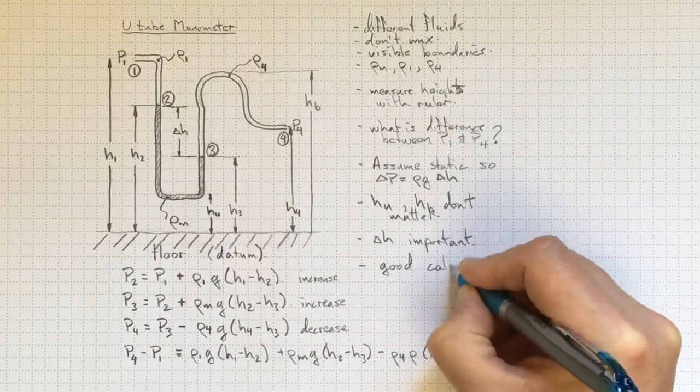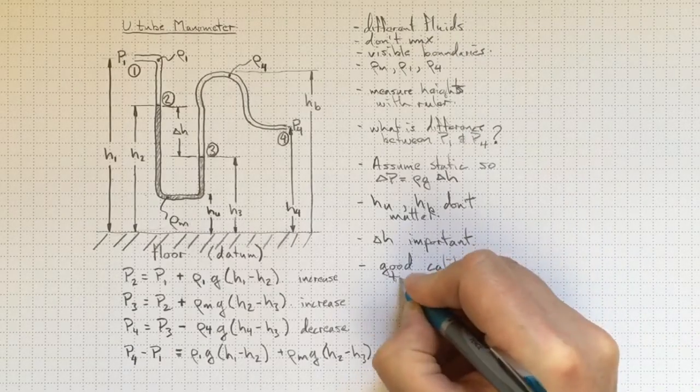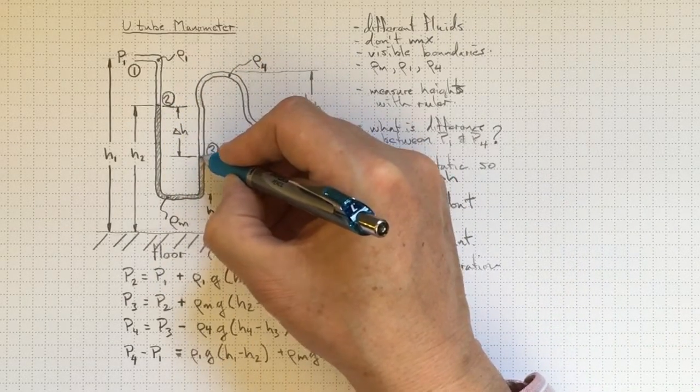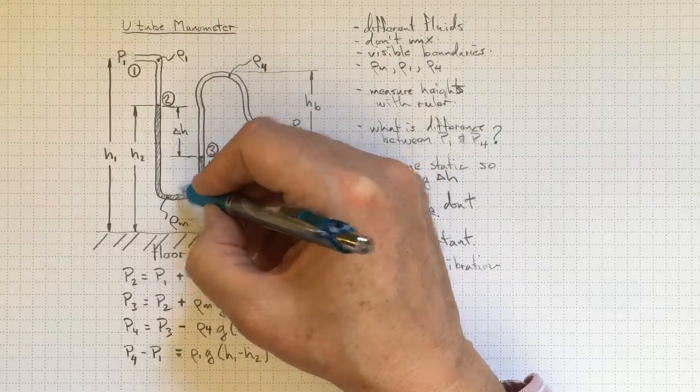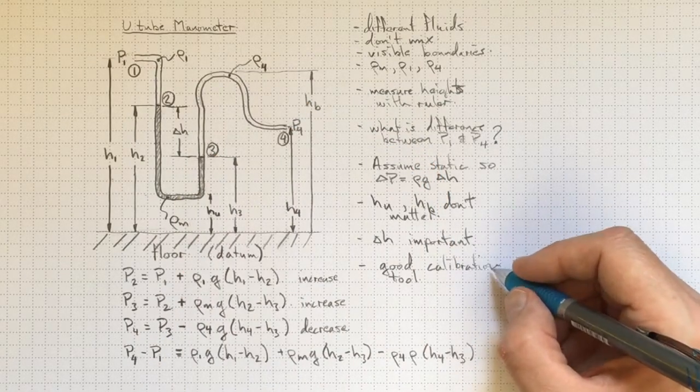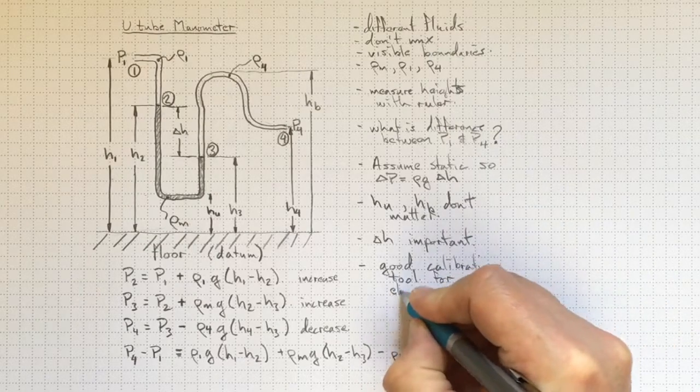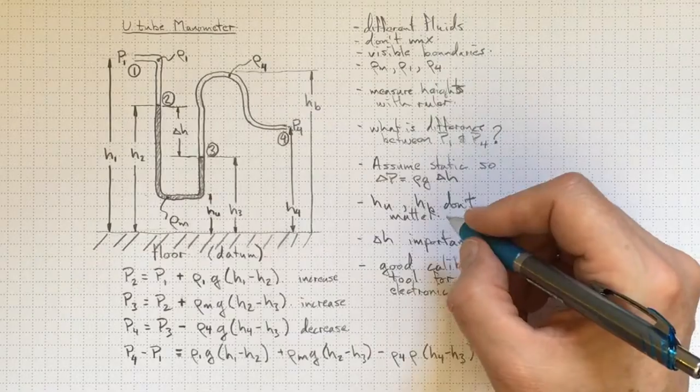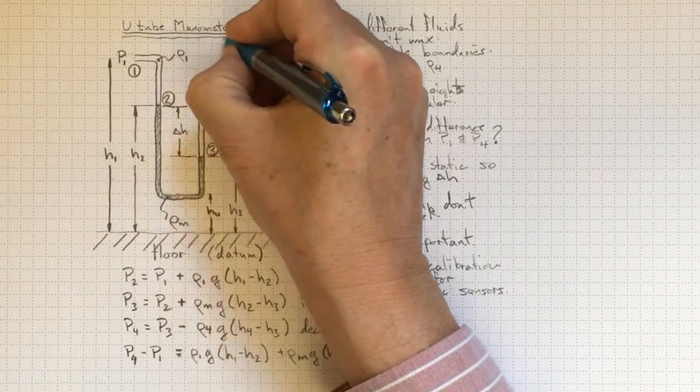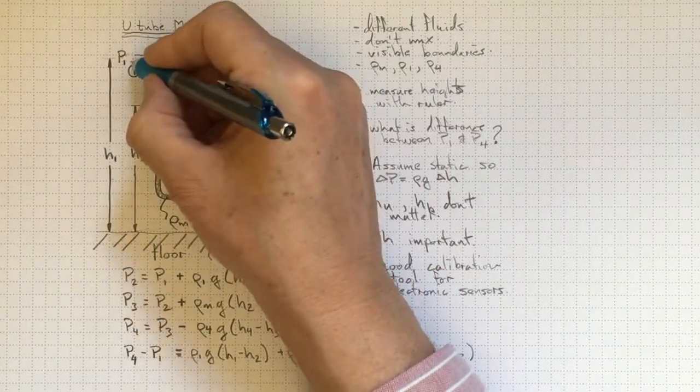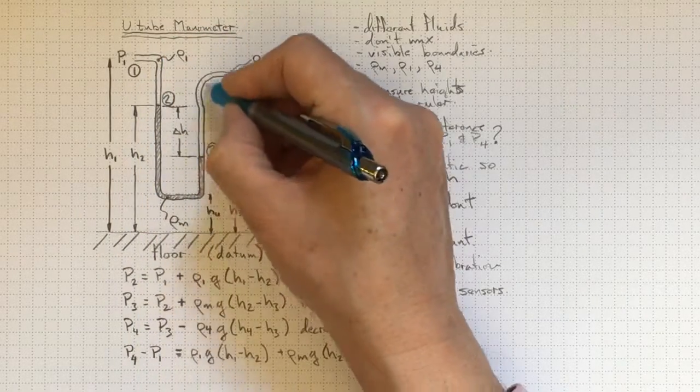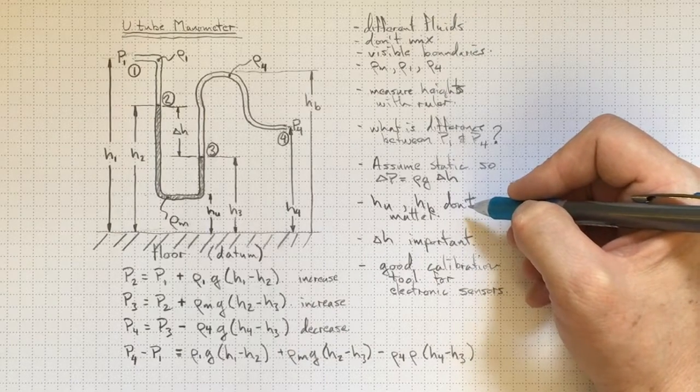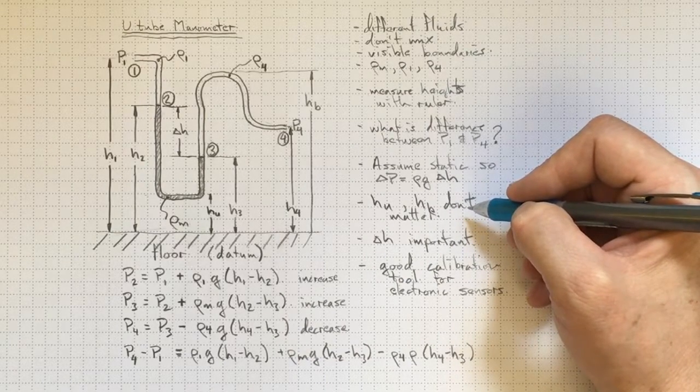This makes a good calibration tool because the difference of a couple of millimeters of liquid is a very small pressure difference, and we can use this to calibrate our electronic sensors. U-tube manometers give us a practical application where we can take what we know about fluid statics, following along a path through a fluid that isn't moving, to determine pressure differences and draw some useful conclusions for practical measurements.